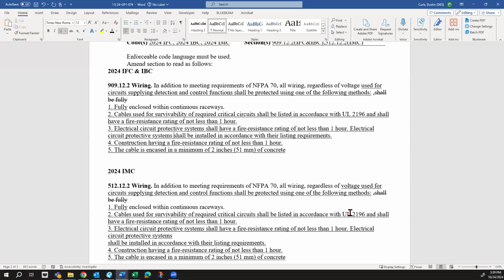Whether or not an electrical inspector enforces that, that's not my world. I can't say, hey, you should have caught this or you should catch that. But when we stamp our design and we submit it and we stand behind our work and we basically say, hey, this system is going to survive, this is what the AHJs can look for. They can reference this and call this out and say, hey, show me how you are doing protection like this. On a design that we would typically do, we would show raceway encased in concrete. We'd show where it's going up vertically with the 2-hour protection. We show how the circuits are isolated from the pressurization system versus what's part of the fire alarm system.